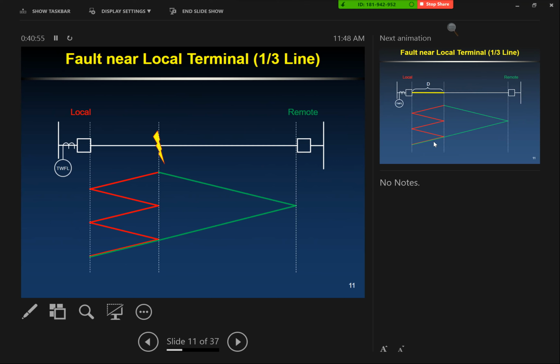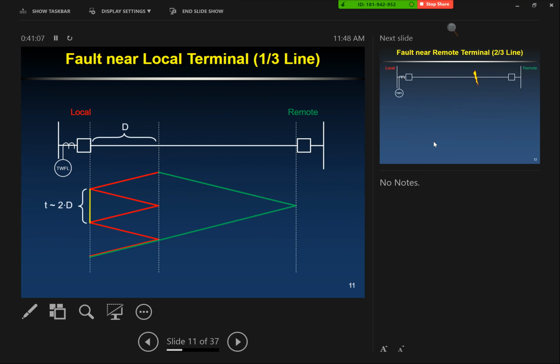What are we interested in when we're doing a single-ended fault location? We want to know that distance from the local terminal to the fault. But we can see visually that that aligns with these two points represented here.